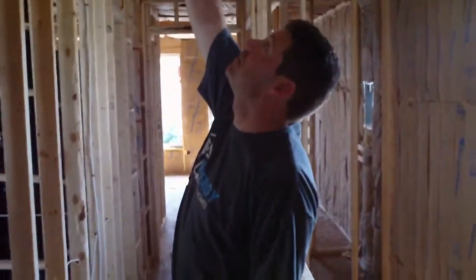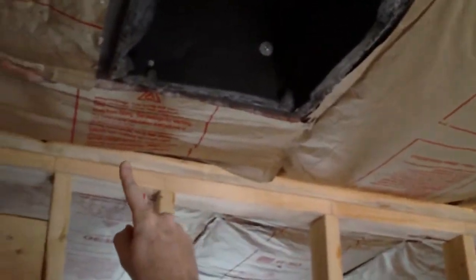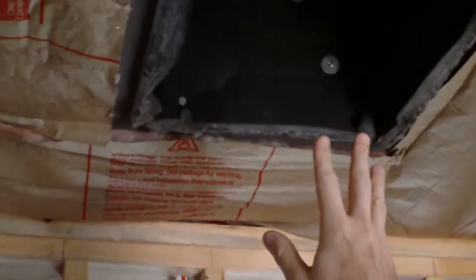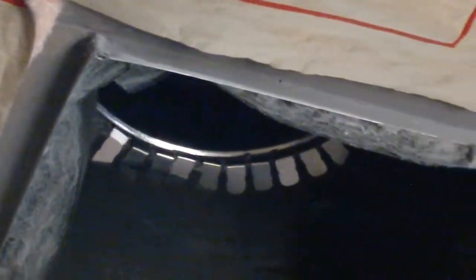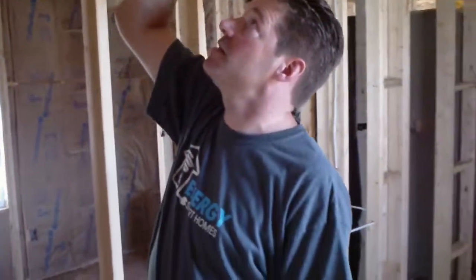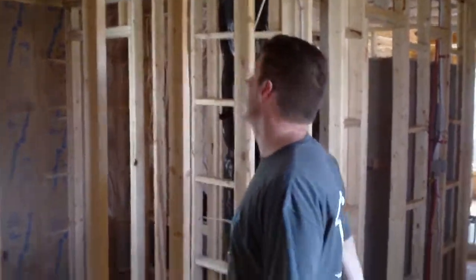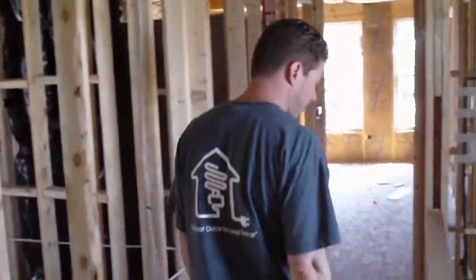They did a good job on their ductwork. You can see the mastic here—they've sealed it to the framing, and we've been upstairs in the attic and checked their ductwork. All of it looks sealed very well with mastic, so tight. Your air coming out of your HVAC units, through the ducts, gets delivered to the house without leaking into the attic or into the structure. So, good job installing that.